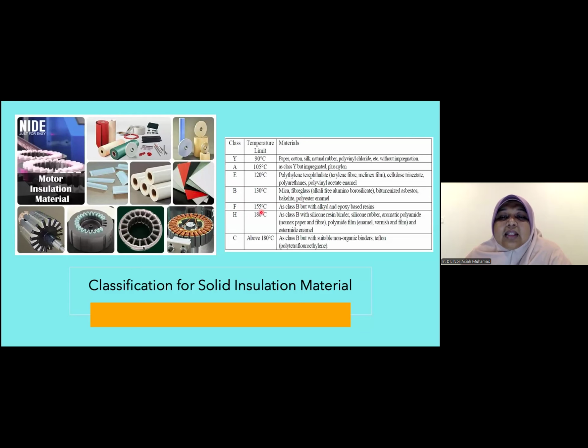We have class F that can operate up to 155 degrees C, which is as class B, but matched with other materials like epoxy resin. Then we have class H, which is up to 180 degrees, which is also class B, that works with silicone resin binder, silicone rubber, aromatic polyamide, mixed with other materials. Then we have class C, which operates above 180 degrees, which is also class B, suitable for non-organic binder like Teflon. So this is the picture of the insulating material. In a rotating machine, this is the rotating part, which is the rotor. This is the static part, which is the stator.